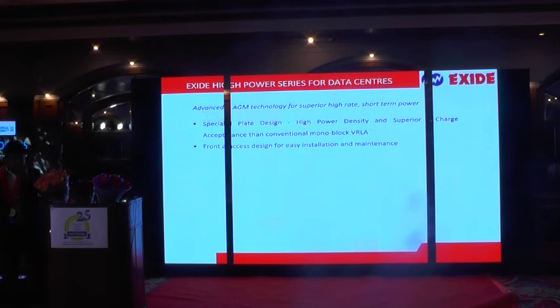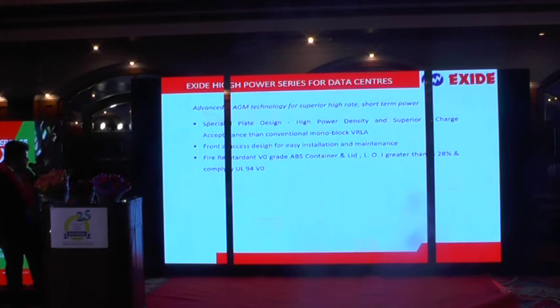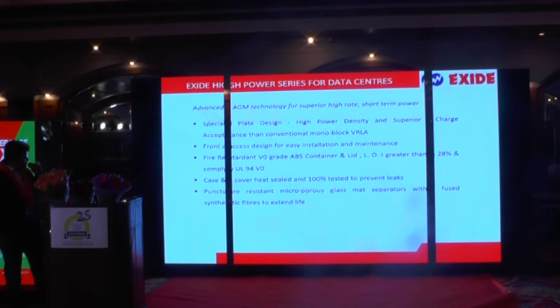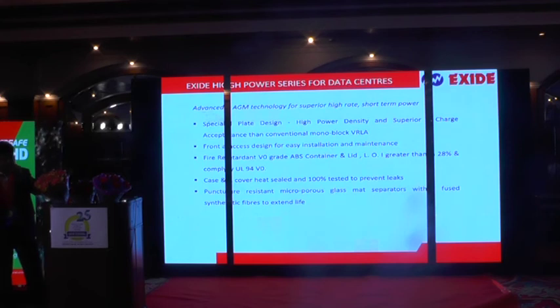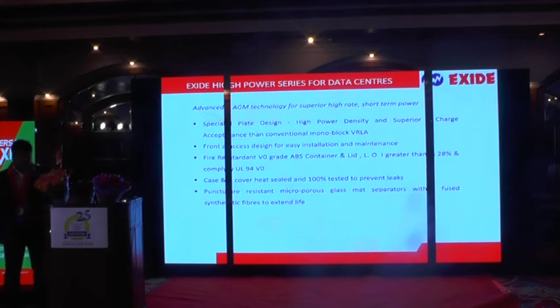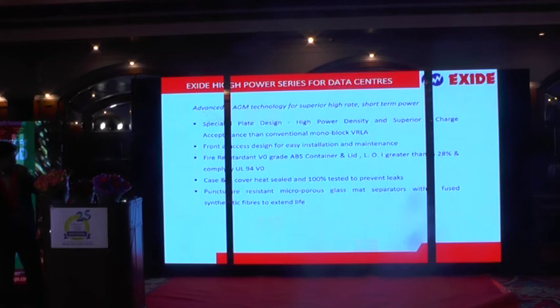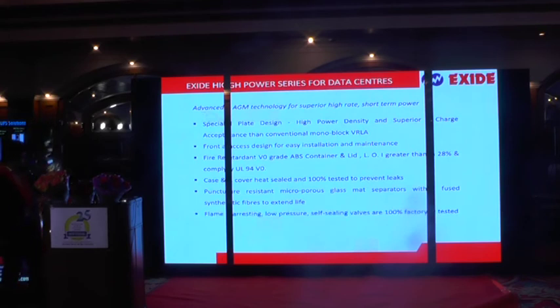The front access design, I will come to that. How does it help? The fire retardant V0 grade is again a safety feature which is absolutely necessary for our data centers. The cover and container are heat sealed and 100% tested. Next most important thing is the glass mat separator. Unlike a conventional AGM separator, this glass mat is fused with a synthetic pulp. This gives a resilience to the separators so that it can undergo a long series of charge discharge cycles. So that imparts reliability. Flame arresting low pressure self-sealing valves are 100% factory tested.